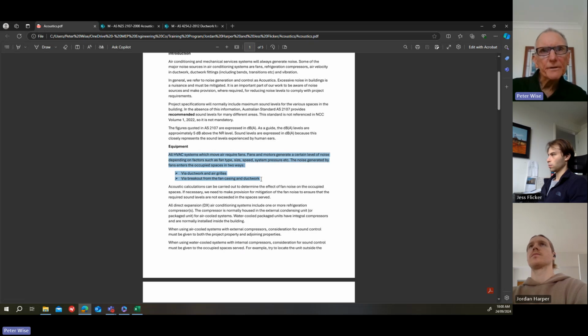Vibration is a very tricky thing. If a fan is vibrating and causing vibration in ductwork, the ductwork is supported from the structure by rigid supports, which is normal. Then the vibration in the ductwork can go through those supports into the structure, and that starts to set up vibration in the structure. It's only minor, but that can show itself as noise in a space.